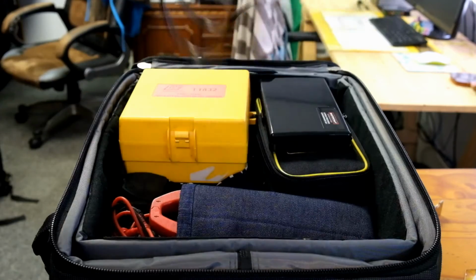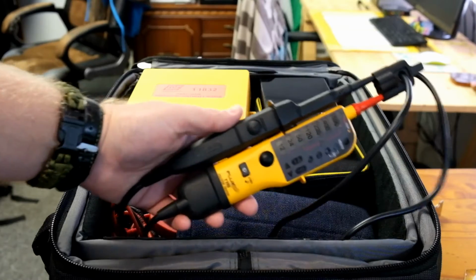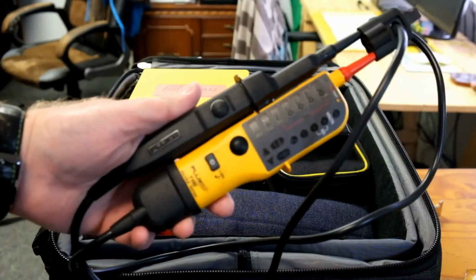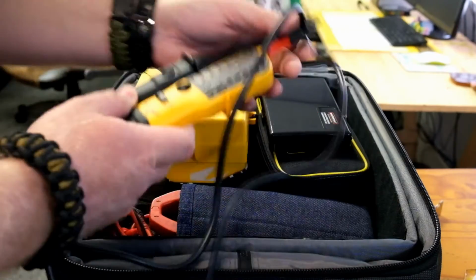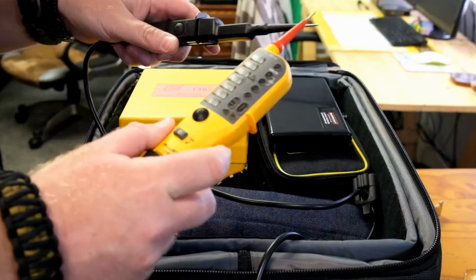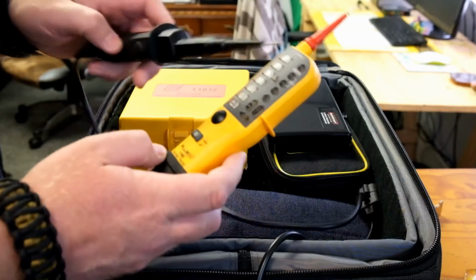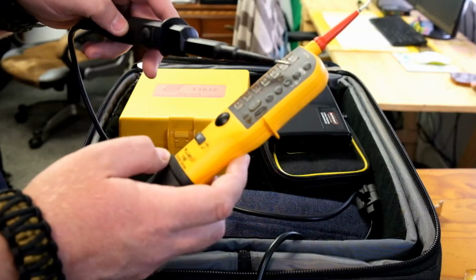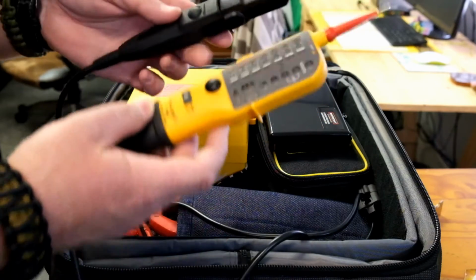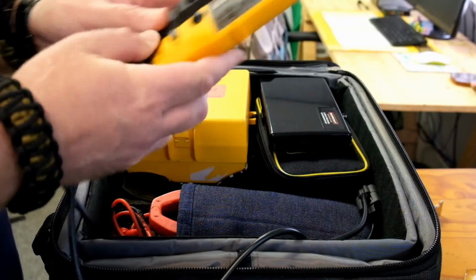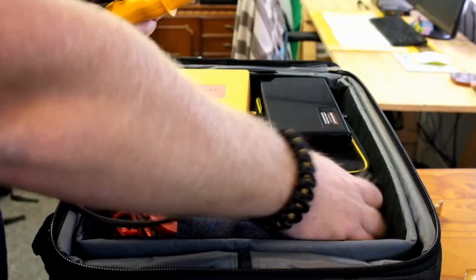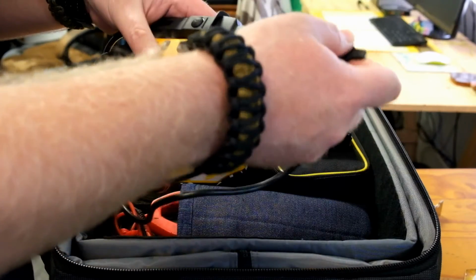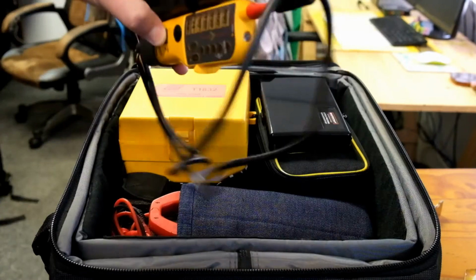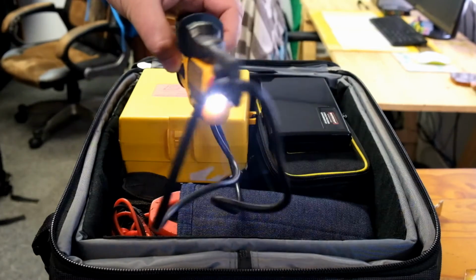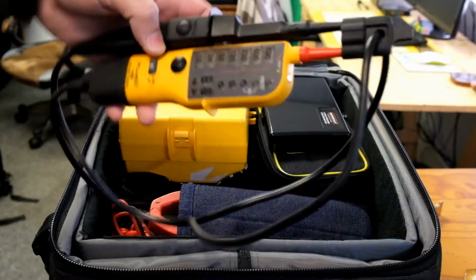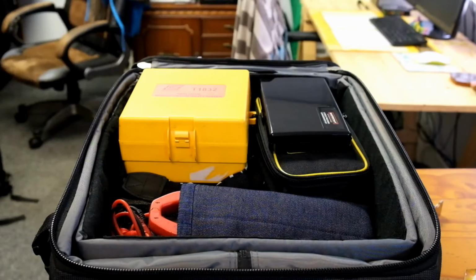Then I've got my Fluke T110, a nice instrument. It's a continuity and volts meter. It tells you about continuity and phase rotation, and if you're measuring DC or AC from 12 volts to 690 volts, it'll give you a reading. As a bonus, it comes with a nice little storage system so the probes don't get damaged, and it includes a little flashlight. Not used too often, but nice to have.